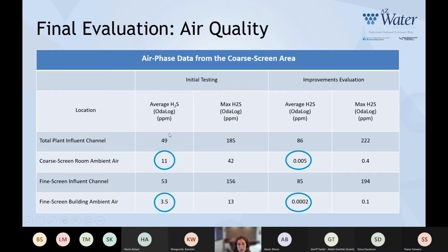General takeaway. I think it's important to point out that if you look at the plant influent channel data, you see a general increase in H2S. But when you look at the room airflow itself, you can see that we had a significant improvement in the room itself. So what that told us was we're keeping the odors down in the channels, and we are keeping them out of the working spaces.